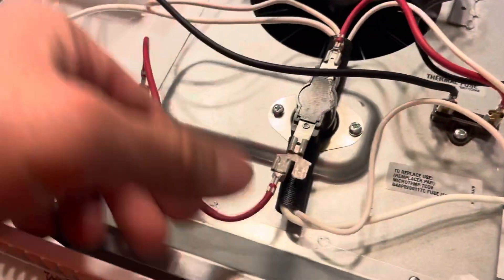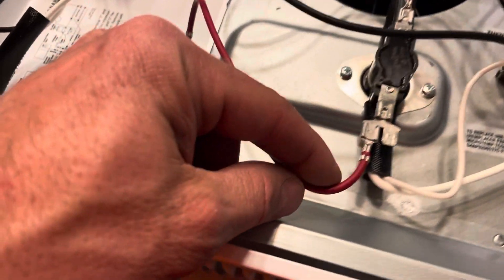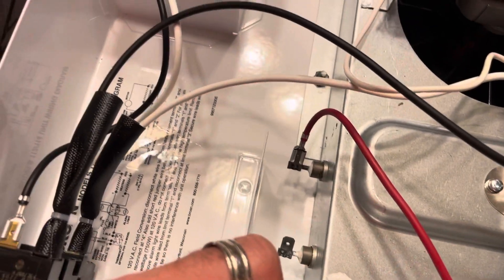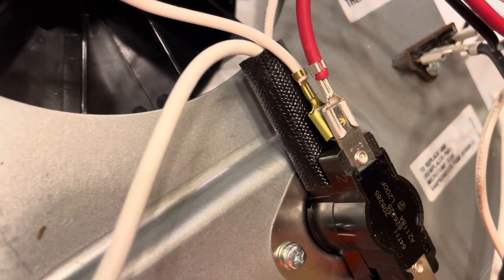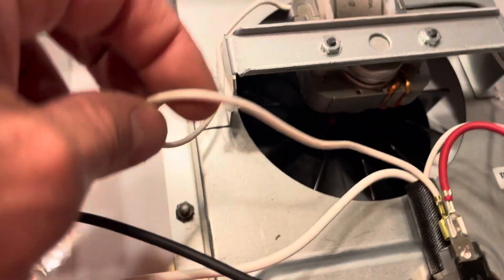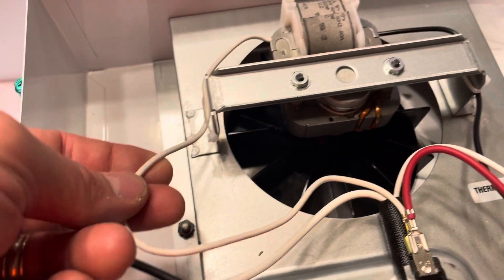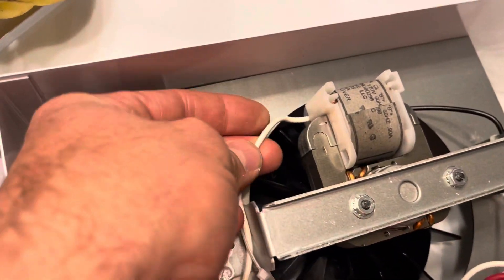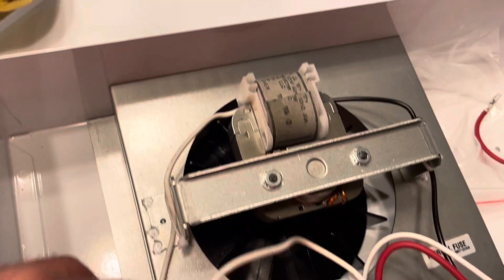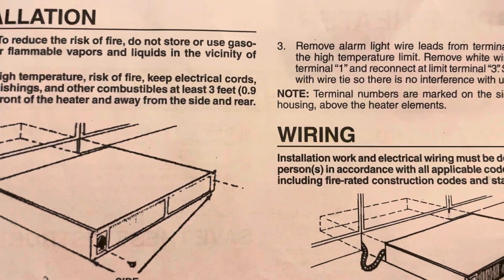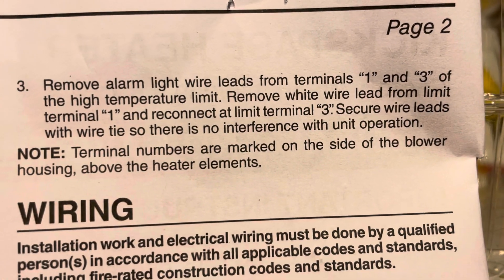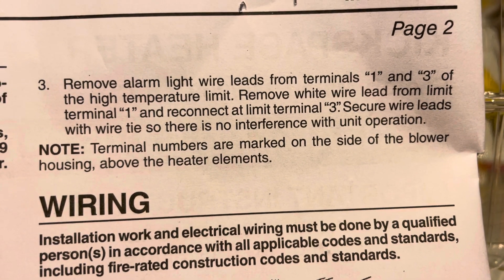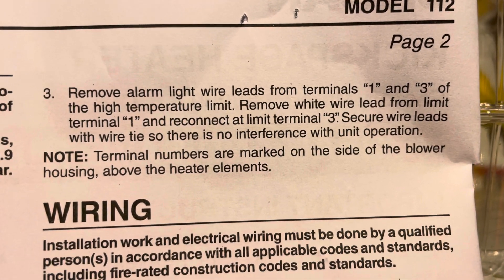So we have disconnected the white wire from here, the only one that was available because these two are underneath in the sheath we're not touching those. Disconnect the white wire and what do we do? We brought it over to this side terminal three. And the other end of that white wire, if you're wondering which one is that, they don't spell it out very clear, but it's actually the motor lead.